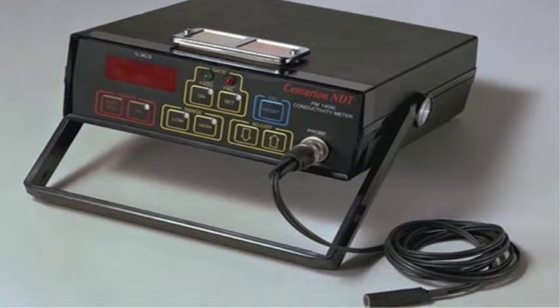The model FM-140XL conductivity test instrument is an eddy current instrument specifically designed to determine the conductivity values of non-ferrous materials. The instrument is calibrated utilizing the two reference samples mounted on top of the instrument. Once this is accomplished, the probe is placed on the unknown material and the value in % IACS is displayed on the instrument. Now, let us see how this is done.